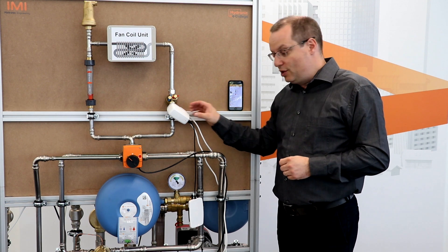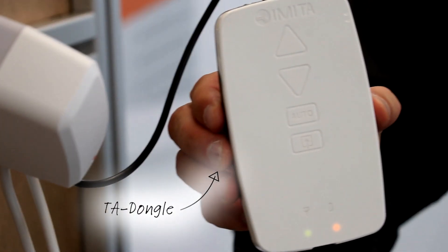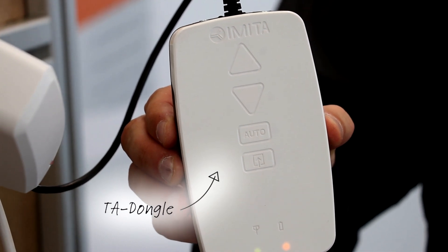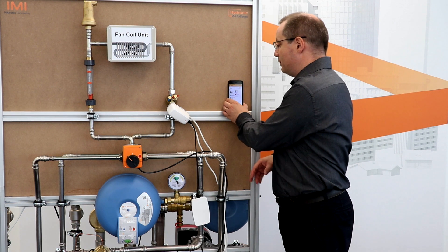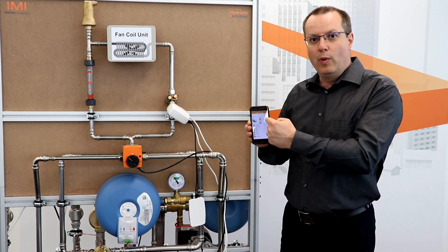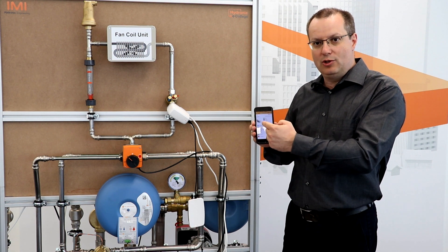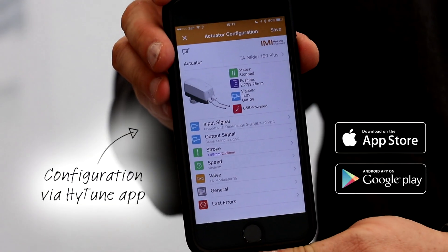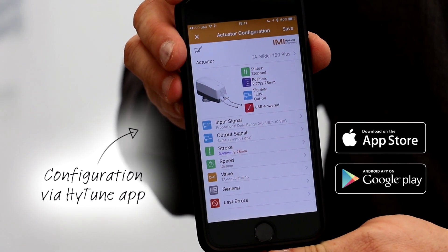The TA slider is a digitally configurable actuator that we can configure by connecting the TA dongle to it and making use of a smartphone, allowing us to parametrize which flow has to be reached when the actuator is switched to cooling mode and which flow has to be reached when the actuator is switched to heating mode.